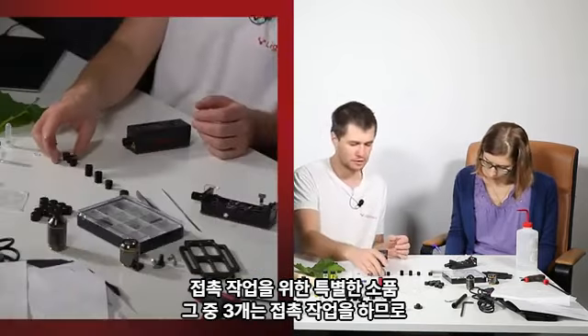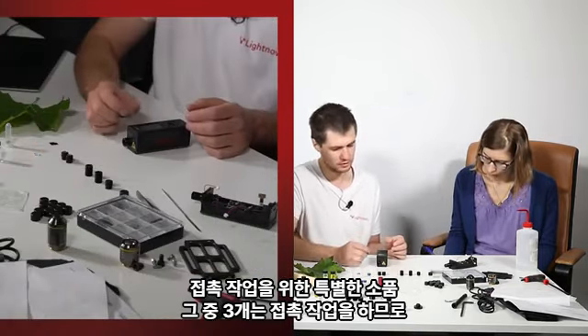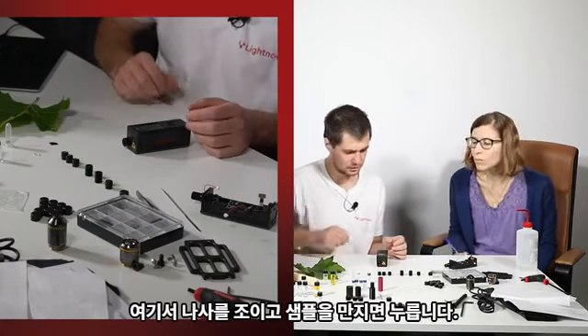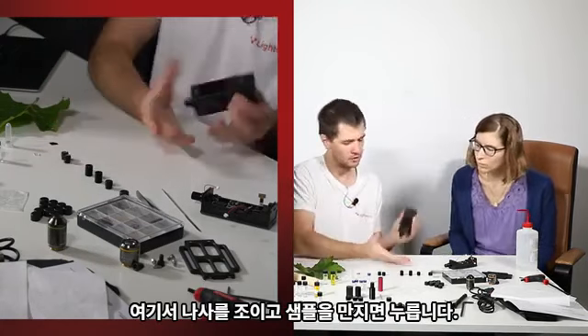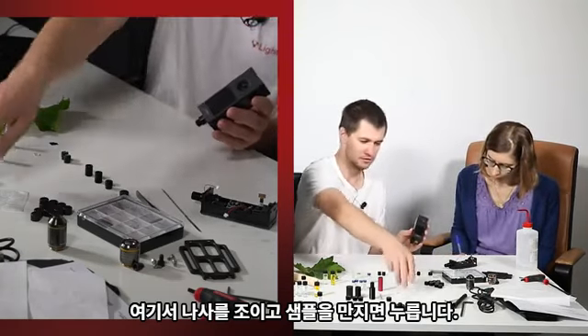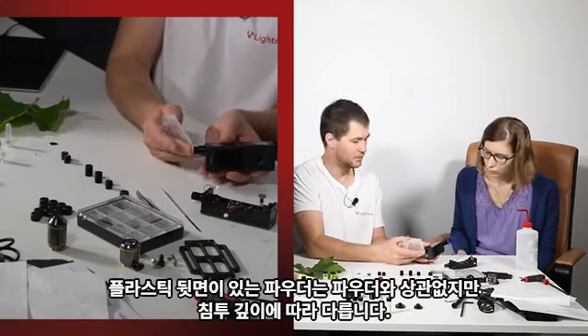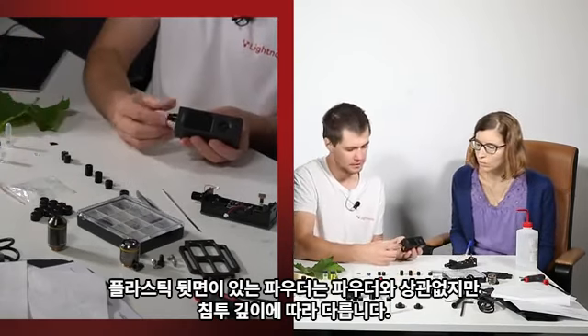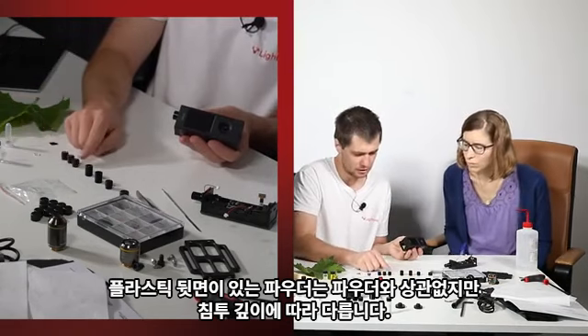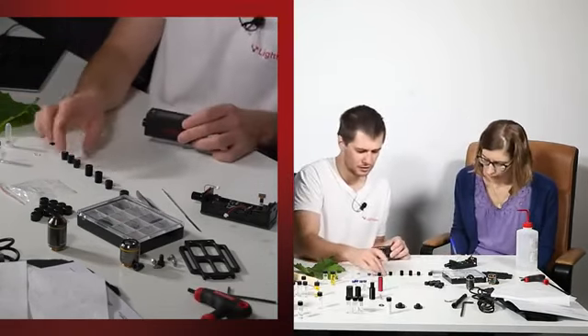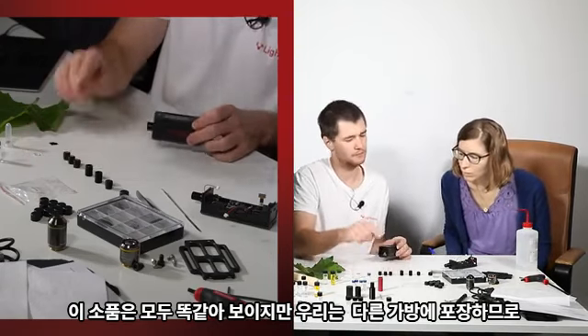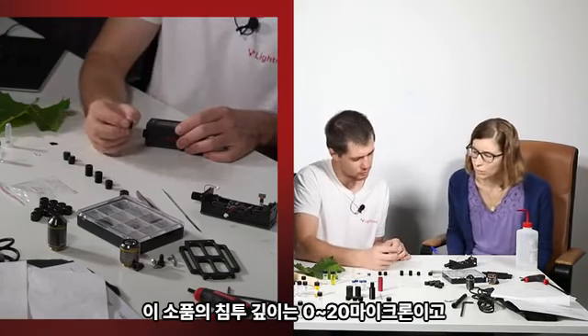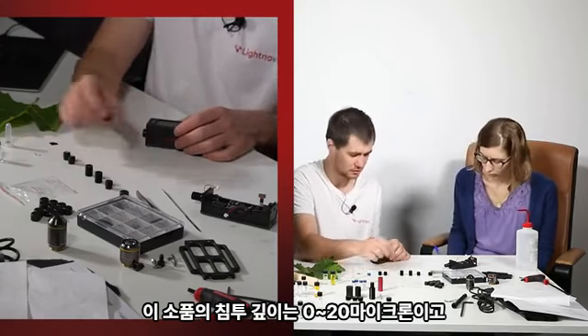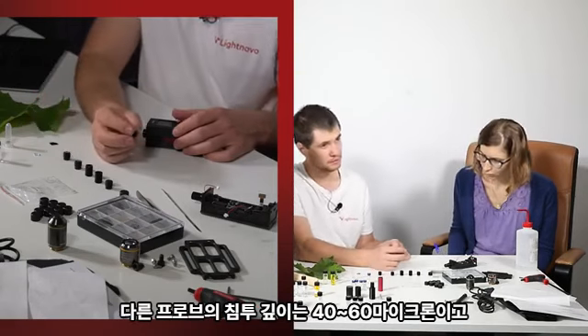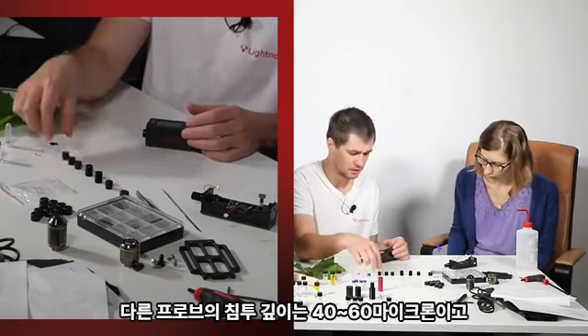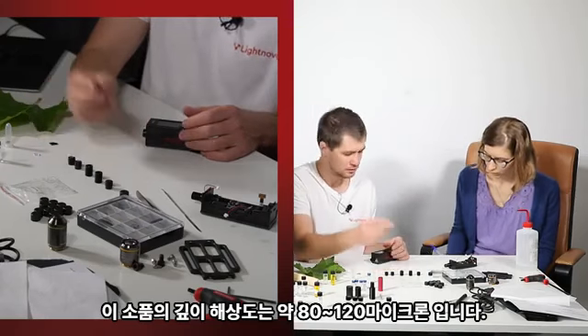Then we have special probes for contact operation. Three of them, and they all work on contact. So you screw them here, and you touch your sample. You press on it. Let's say powder in a plastic bag, whatever. But they differ by the penetration depth. The probes all look the same, but we pack them in different bags. So this probe has penetration depth 0 to 20 microns. Another probe has penetration depth of 40 to 60 microns, and this probe would be around 80 to 120 microns.